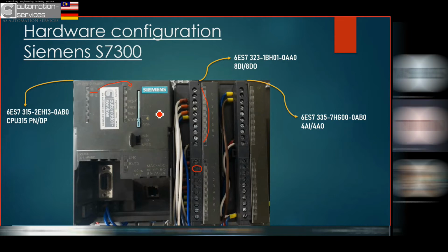Number two, for example, is if I already configured these two cards here, two slots, and suddenly I take out one slot, or one module is broken, then it will give a system fault because the configuration is not complete. There are a few more system faults, later we will see.